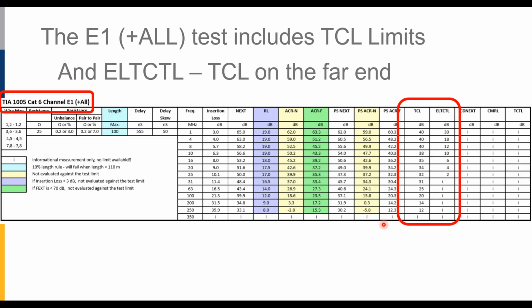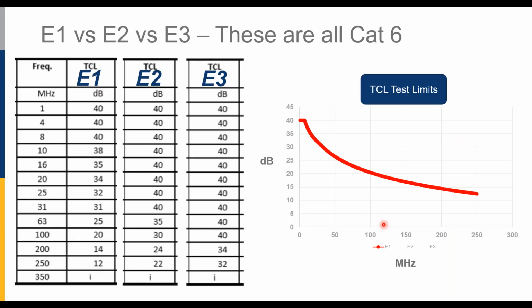And we're also going to test TCL's friend, ELTCTL, which is TCL measured on the far end, a little bit like far end crosstalk. So this is the big difference between an E1, an E2, and an E3 environment when we talk about, say, category 6 cables. These limits are going to 250 megahertz. So here are category 6 limits, the strength of the TCL in decibels versus the frequency. And the return loss and the insertion loss are all the same across the M.I.C.E. 1, M.I.C.E. 2, and M.I.C.E. 3 environments, but it's the TCL that is going to be stricter.